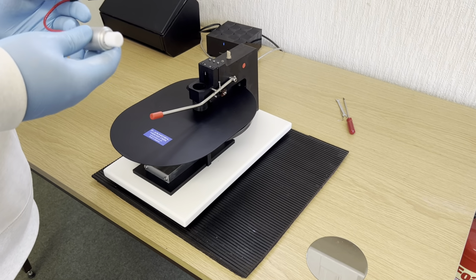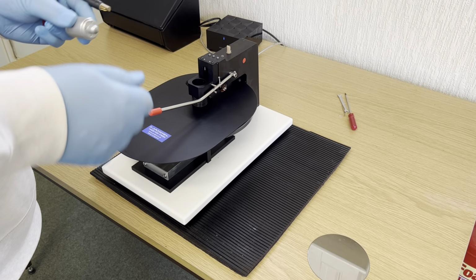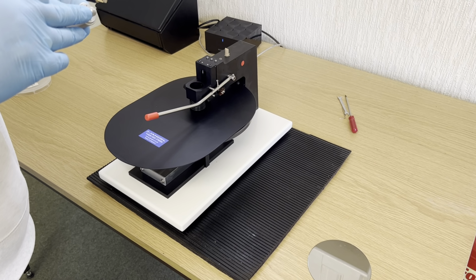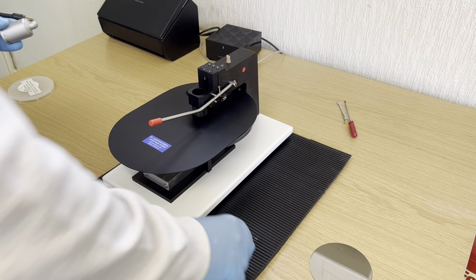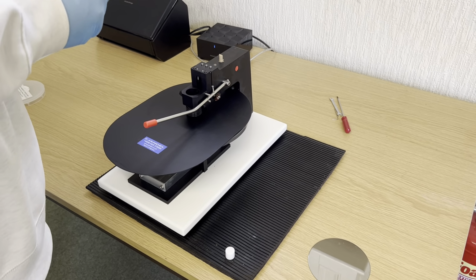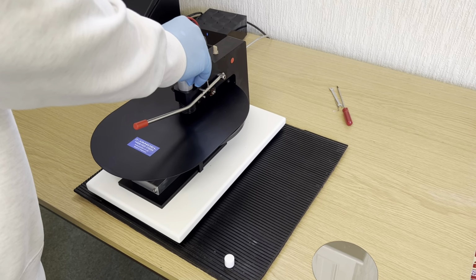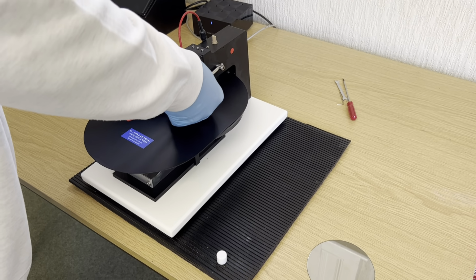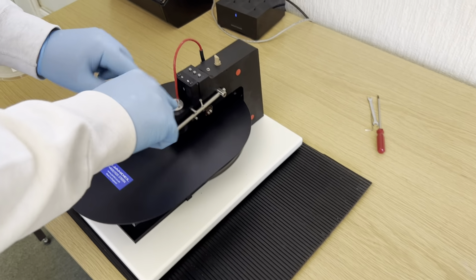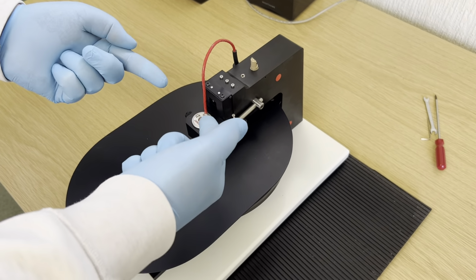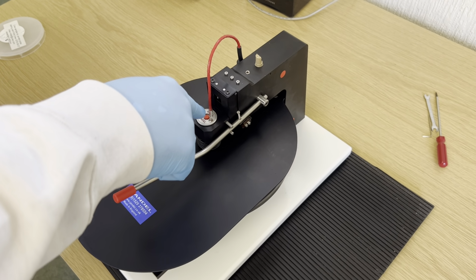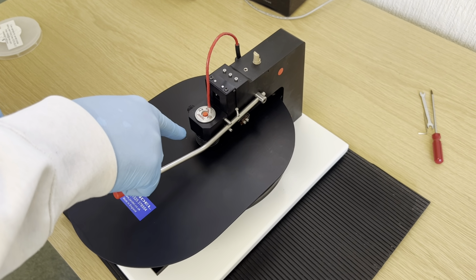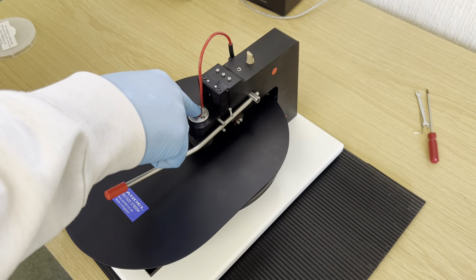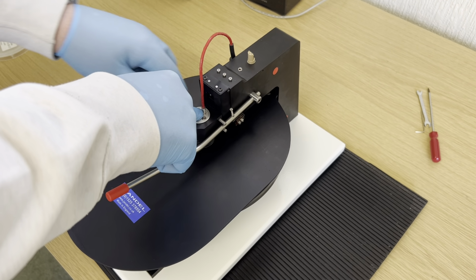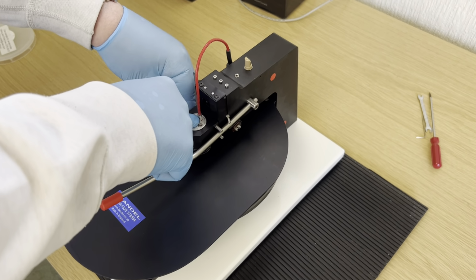The 4-point probe has a protective cap which needs removing to expose the 4 points. To position the probe, place it over the bellows and push down with the bellows coming up the side of the probe. The probes are now touching the sample. Press down firmly on the probe head and secure in position.